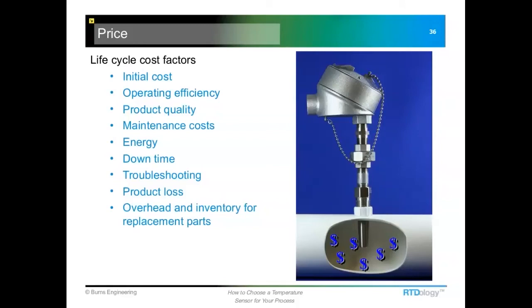And so, getting into the price of this installation, as we saw, a bad, inaccurate temperature measurement can be very costly. Usually the initial cost of the sensor is one of the very smallest things there is. We have to look at not only the energy usage, but the maintenance costs. If it is a poorly designed sensor or poorly installed, if we had some vibration going on in our pipeline here, the thing might vibrate and fail prematurely, so we've got to go in there and replace it, which means a lot of downtime and a lot of troubleshooting. You may lose some of your product, and then we've got spare parts that we have to keep in stock or try to source. And generally, you need it in a hurry if it fails unexpectedly.